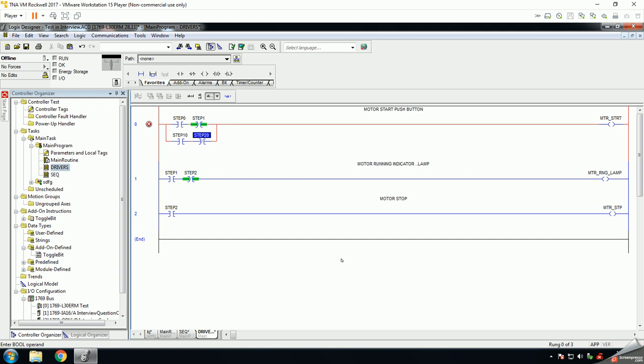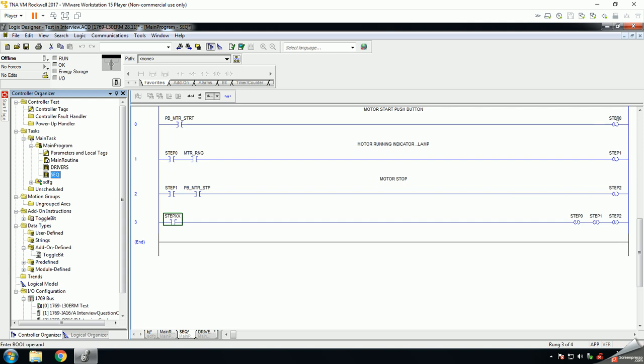And like I said, very easy to do. But obviously this has its problems as well. There's no perfect design pattern out there, and straight away I can tell you, going from step 0 to step 1 is probably a bit of a no-no. You want to maybe say step 0, then step 10, and then 30, and maybe even step 0, step 100, 200, 300, 400. So what? It's just a number at the end of the day. You can have 32,000 numbers, so you could make them up in hundreds. It doesn't have to be tens, and then you can add steps in there easier.